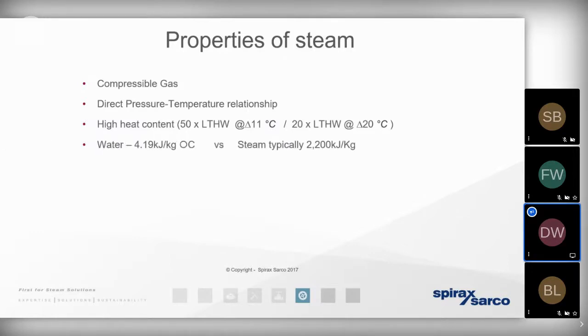And we remember that that information is really based on the understanding that water, the raw ingredient of a steam system, water's got a specific heat capacity of 4.19, meaning if we want to increase the temperature of 1 kilogram of water by just 1 degree, well, we need to add 4.19 kilojoules of energy to it. That information is the cornerstone of the steam tables that we'll come on and review in a couple of slides' time. We also know steam as a gas, well, we don't pump it. It moves in accordance with the pressure drop around the distribution network. So we need a good motive pressure, not only to push the steam towards the process, but to then energize the condensate and push the condensate across the steam trap so it can return back to the boiler house again.